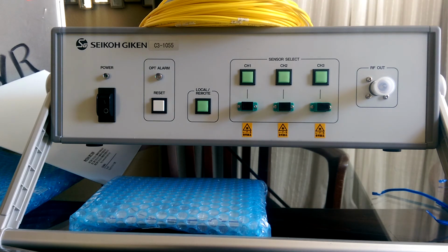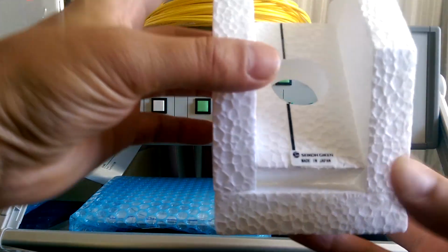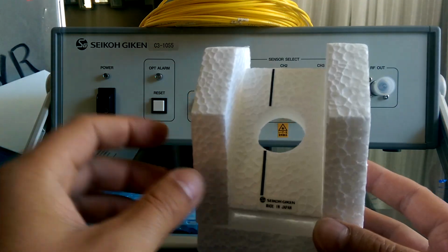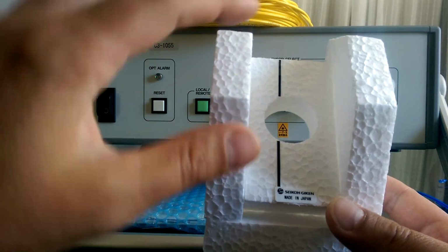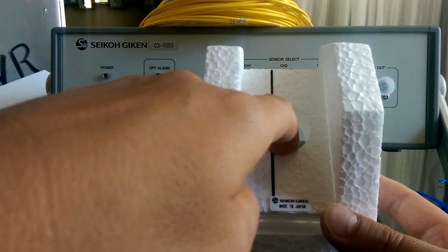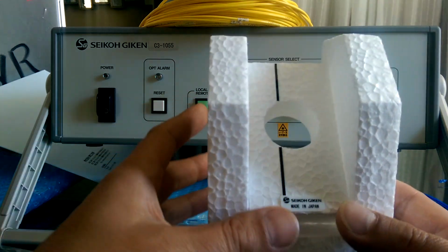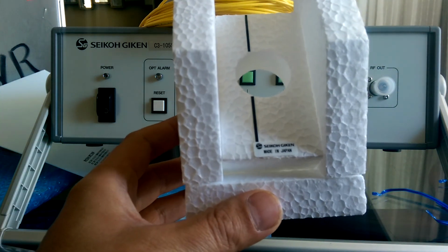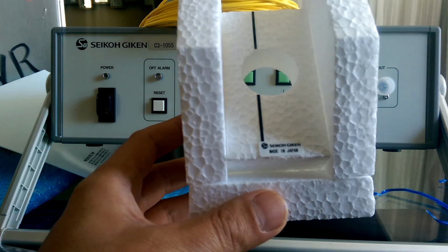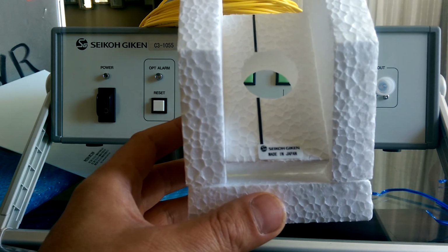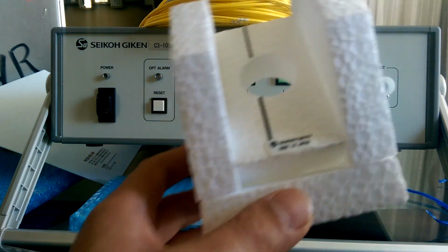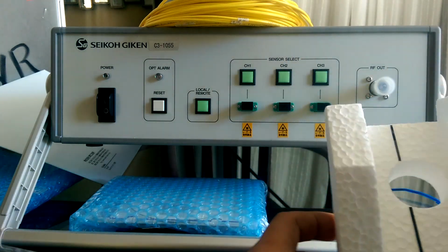Now the next one is the sensor head that I want to show you, the SH03EX. I'll show you how this fits into the positioning jig, which is here. See, on the positioning jig, this is the front of it here, and this is where you're going to be sliding the sensor down into. There's this black line, and that's where you're going to want to align the single side of the channel 1 on the prism on the back of the sensor. I know that doesn't make sense right now, so I'm going to just show you.